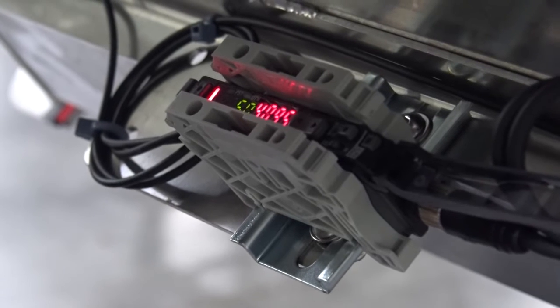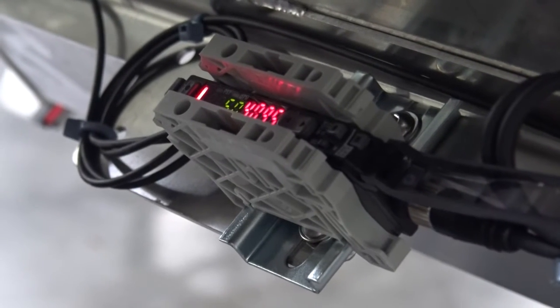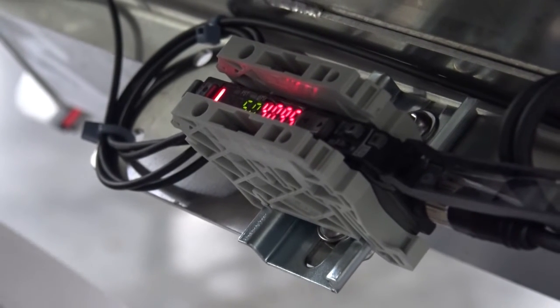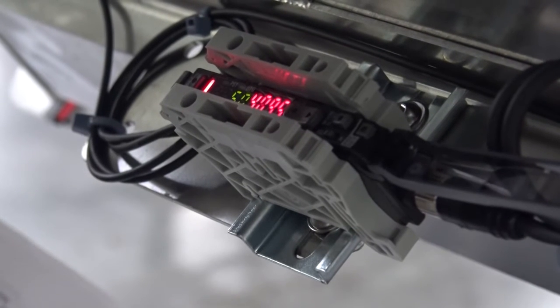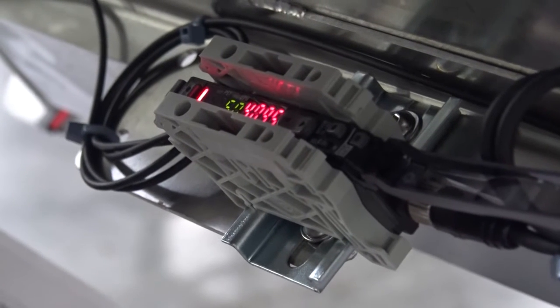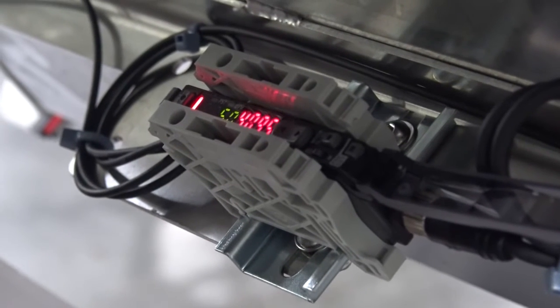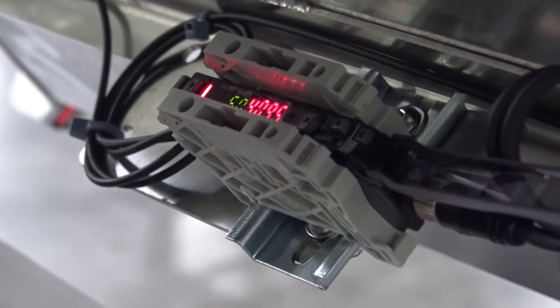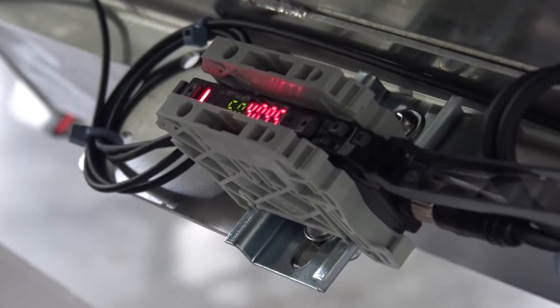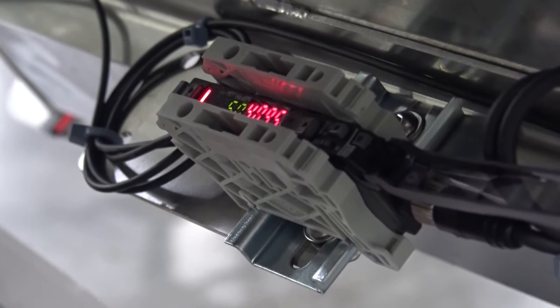Section C of the setup procedure. The standard factory default setup of these light sensors is a high intensity light. That is too much saturation of light for this application, so we want to bring down that amount of light to about half of what it produces. So in terms of units right now, factory default, we're going to give about 4,100 units of light, and we want to bring that down to about 2,050 units of light to pick up these high-speed, smaller product of French fries.